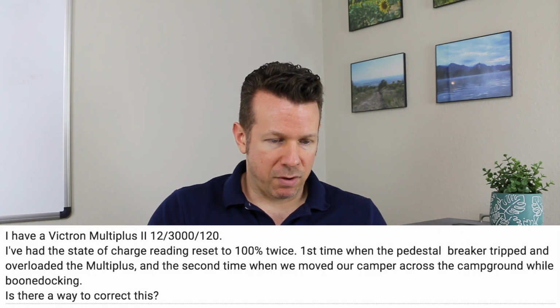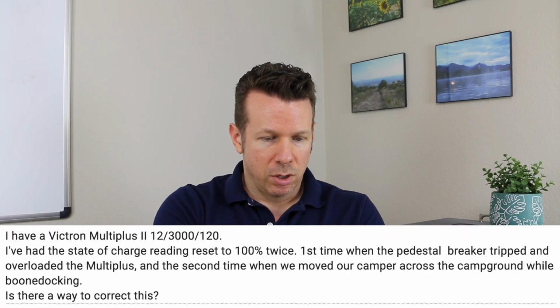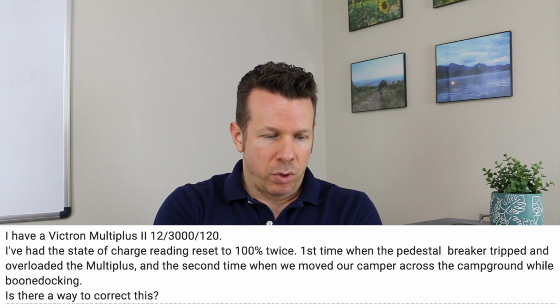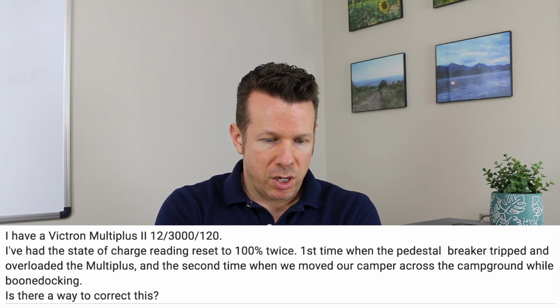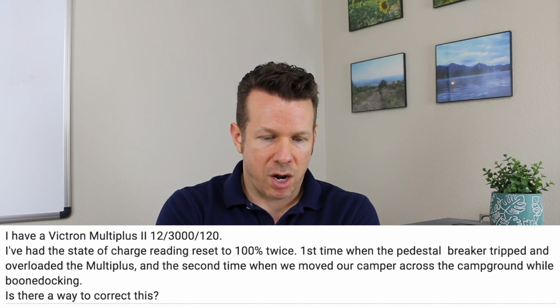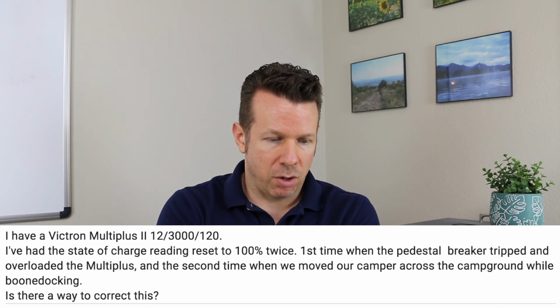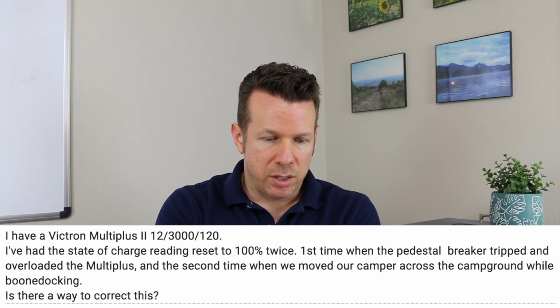Great question, Susan. Bob says, I have a Victron Multiplus 2, 3000/120. I've had the state of charge reading reset to 100% twice. First time when the pedestal breaker tripped and overloaded the Multiplus, and the second time when we moved our camper across the campground while boondocking. Is there a way to correct this?